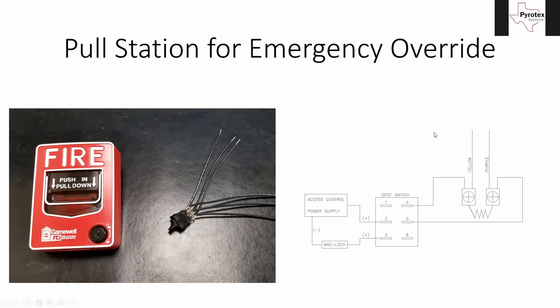Looking at the diagram on the right, terminals one, two, and three are connected: two is your common, and one and three are your two switch points. Same with four, five, and six: five is your common, and four and six are your two switch points. The two sides are in no way connected horizontally — whatever you wire to four, five, and six has nothing to do with what's wired on one, two, and three. This one switch lets us control two separate things, replacing the switch that normally goes inside the pull station itself.